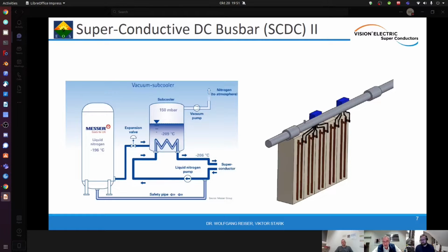And then we have a DC converter, which is very efficient because we only convert DC to DC. We convert 500 volt, for example, or any other voltage coming out of the battery, to 48 volt DC or any voltage which is required on the OCP rack, or we convert to 24 volt or whatever. That is something very easy to do, and very efficient in the process itself.